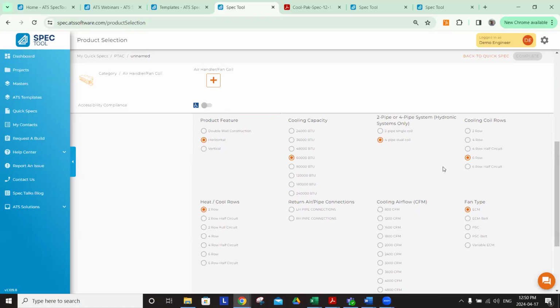Once this unit is on the spec and it's time for shop drawings, that's when we need to nail this unit down to exactly what it needs to do. But if you select this unit and you say, yep, this is what I want to put onto my project, if I see this, or if the ATS specification reps see it, we're going to call you and say, hey, let's take another step. Let's contact the manufacturer. I've got a program called eSelect from First Company that I'll build this unit in for you. I'll put in the water temperatures that you're using, the flow rates, the airflow, the static pressure. I'll build this unit and hand you a spec sheet that says this is exactly what unit you need. These are the rows that we're going to need to accommodate the capacity that you're looking for. And this is the unit that needs to be on your schedule.